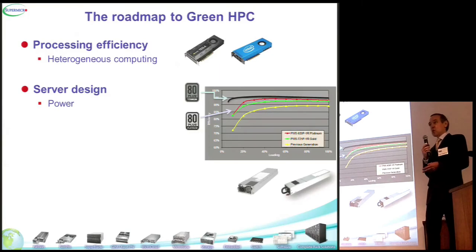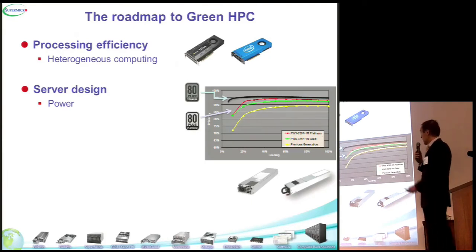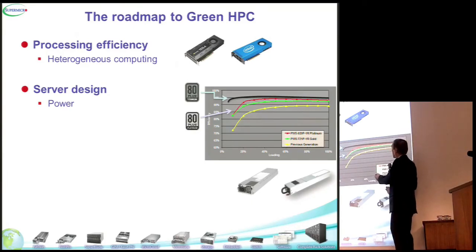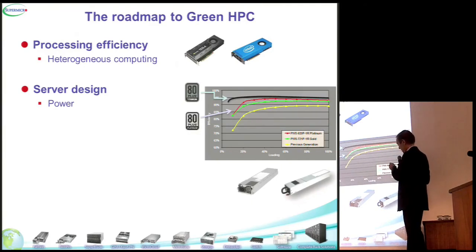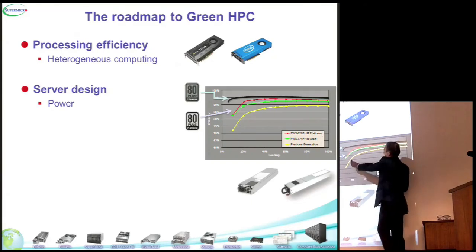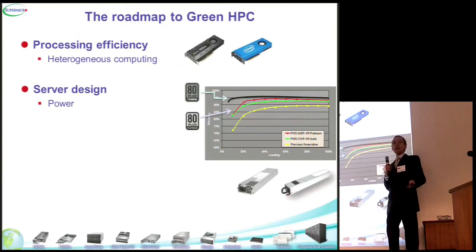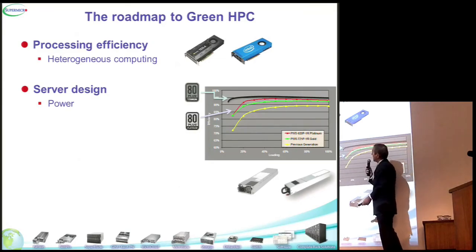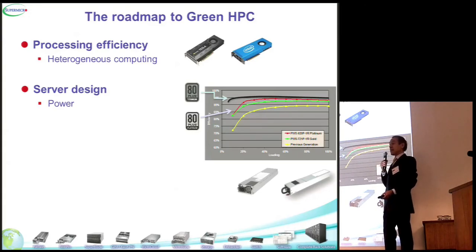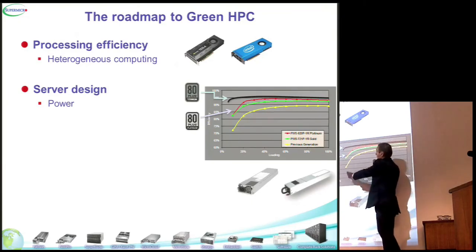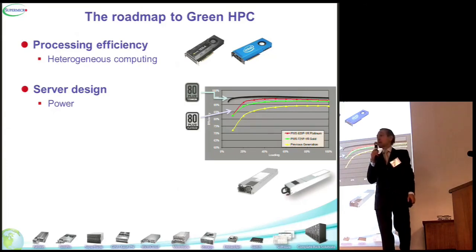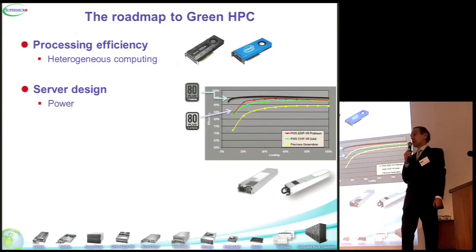Many times a cluster is not working full load, it's working with a low load. Even a Platinum 80 Plus, a measurement of power supply efficiency, with a 20% load will have an efficiency of perhaps below 90%. There is a new grade of power supplies, the Titanium grade, where you will hold 95, 96% efficiency even in loads as low as 5%.